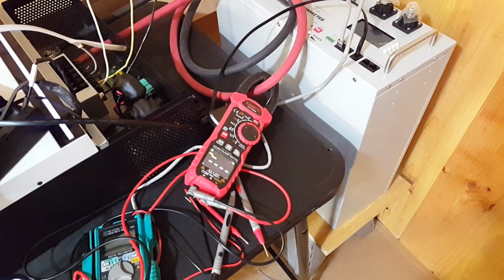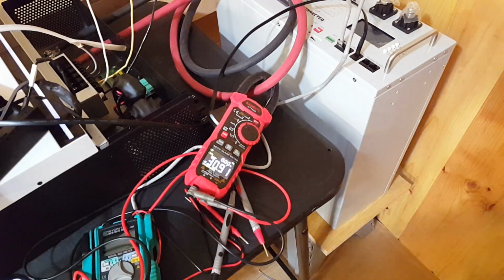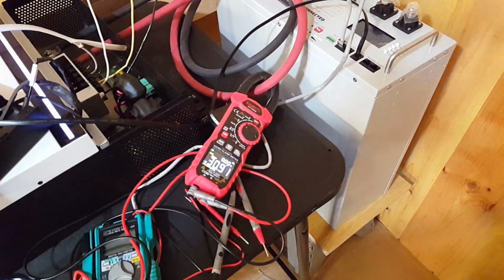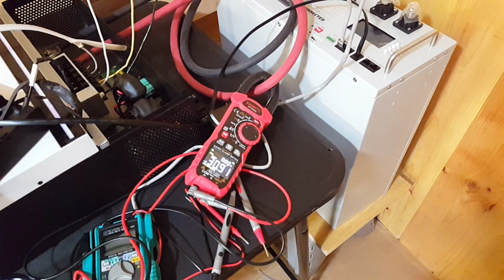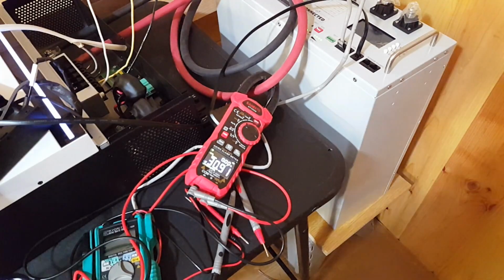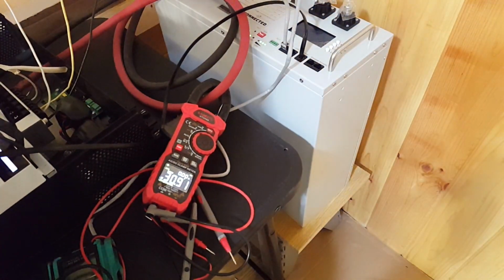Just a quick reminder, at this point, we are still testing all the loads individually. We got one more left to go. After this grinder, it's going to be the table saw. And I think it's going to fare even worse because I have measured the AC inrush on the table saw. It's still higher than this grinder and the air compressor. So I don't expect it to do well for that. I know that already, but the fact that sometimes it will fail for the grinder and the air compressor, that's disappointing. Battery has reset. Go back to battery mode.